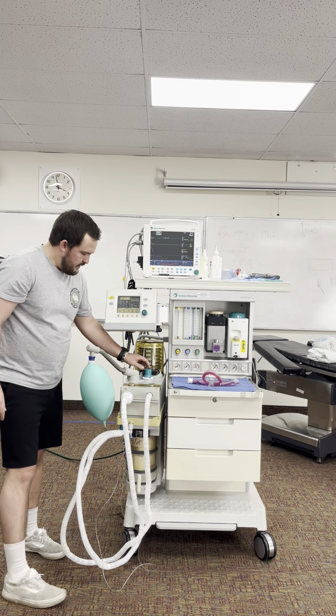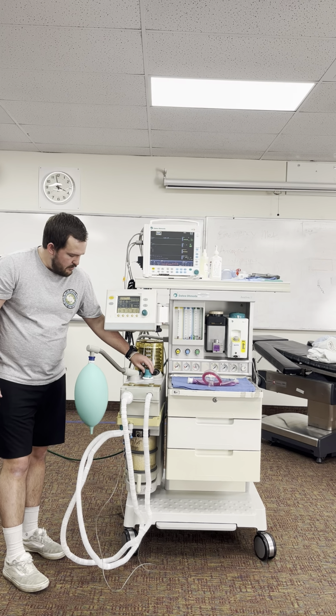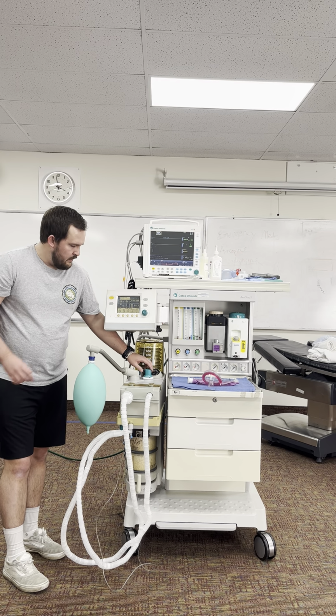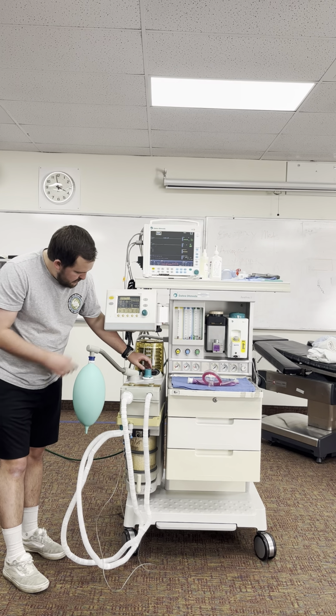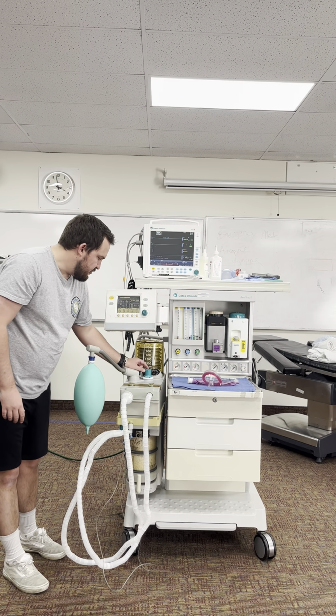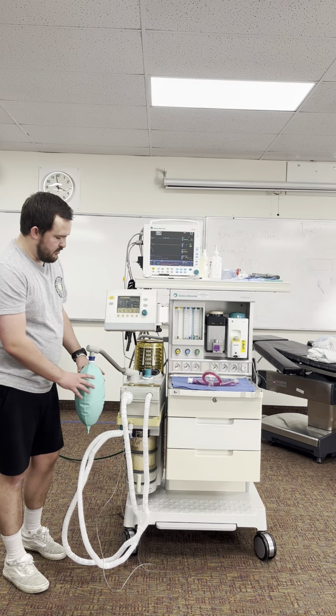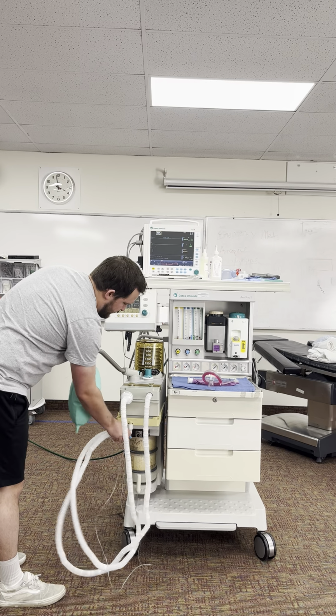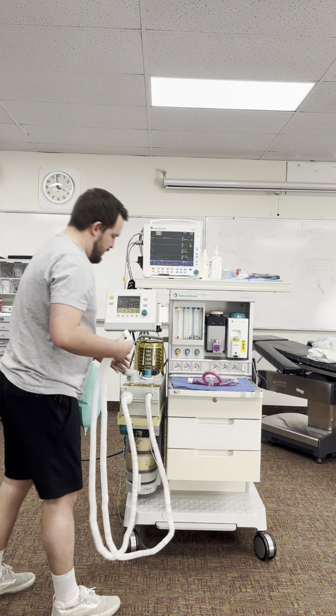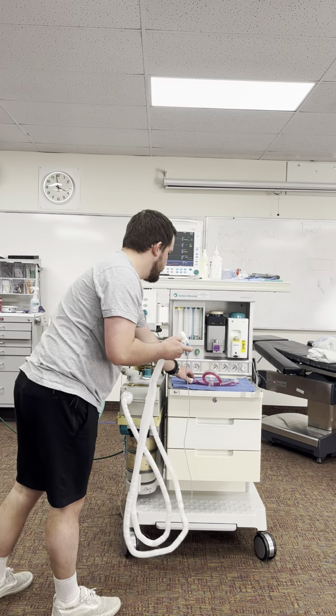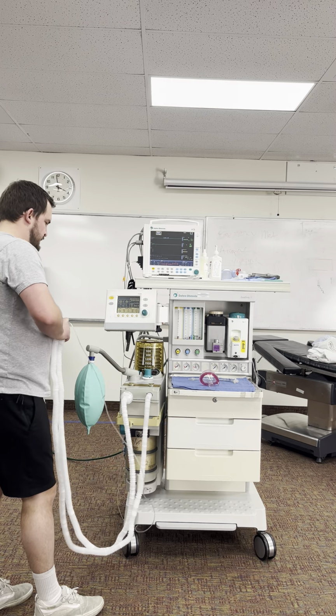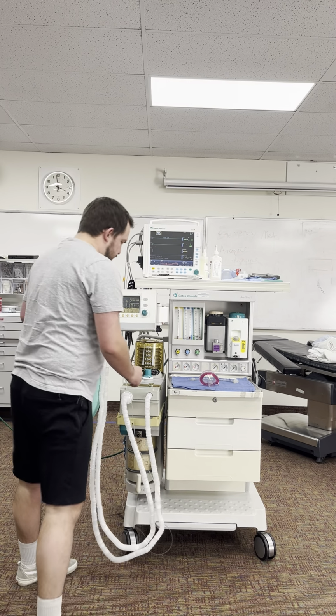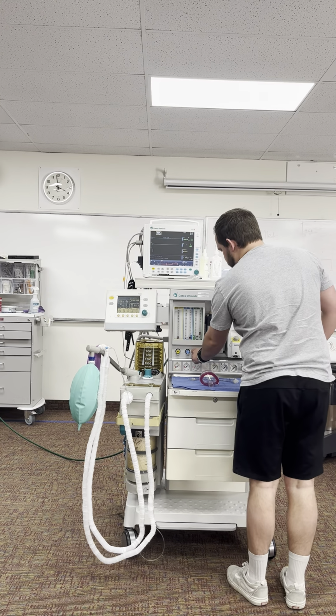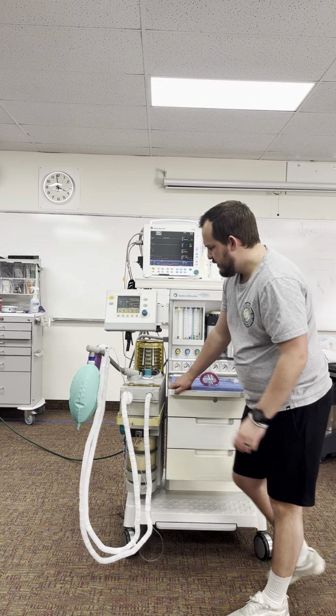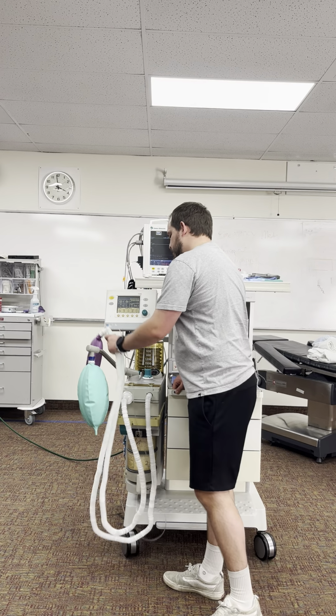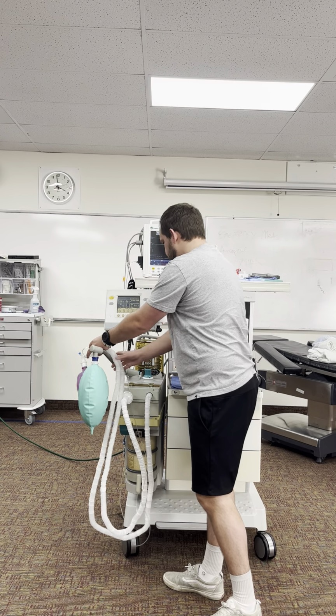Good. So now as I lower or open my APL valve back up, I'm gonna go 30 to 20. The pressure gauge should follow, and as I decrease, it'll continue to follow it down until I'm open and the pressure's back and it's been released. So now, we're gonna connect to our artificial lung. And I'm going to increase to 2 liters. And although I would never do this with a patient that's actually connected, I'm just gonna do this to make sure everything's up and inflated.